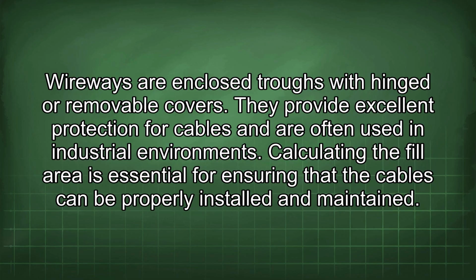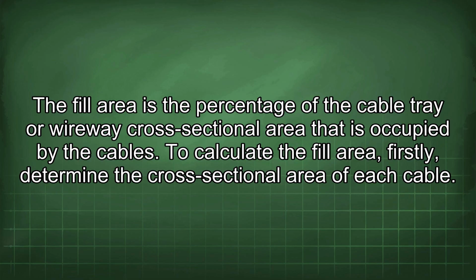Wireways are enclosed troughs with hinged or removable covers. They provide excellent protection for cables and are often used in industrial environments. Calculating the fill area is essential for ensuring that the cables can be properly installed and maintained. The fill area is the percentage of the cable tray or wireway cross-sectional area that is occupied by the cables.